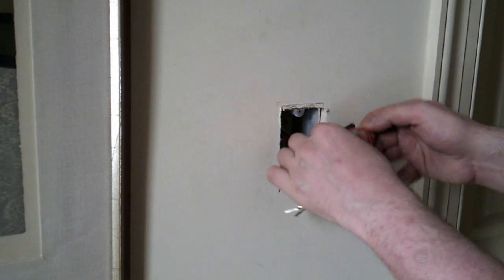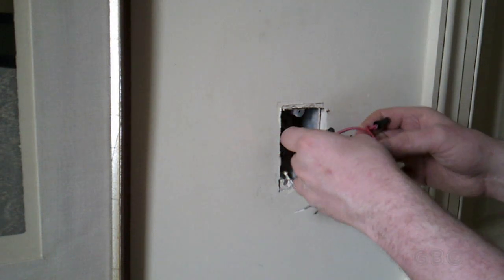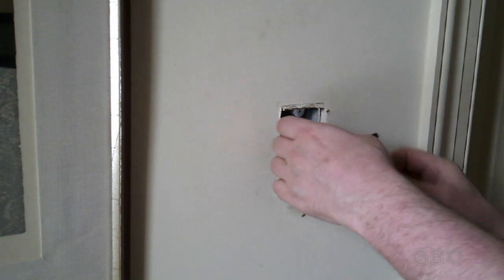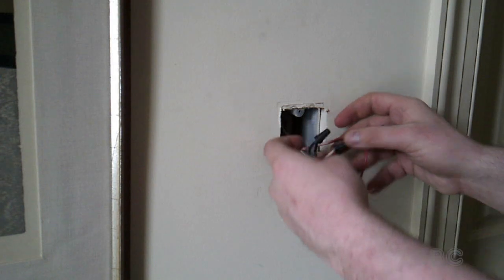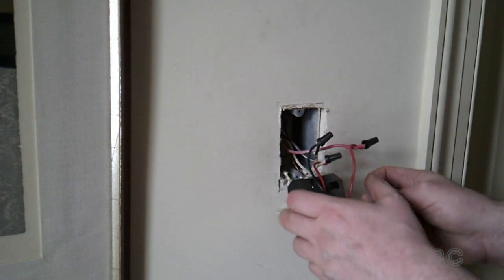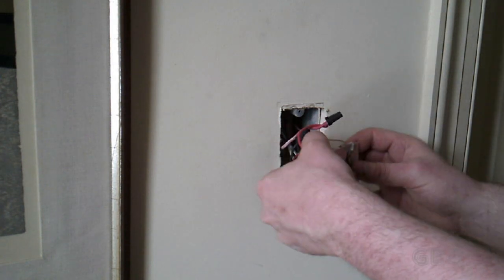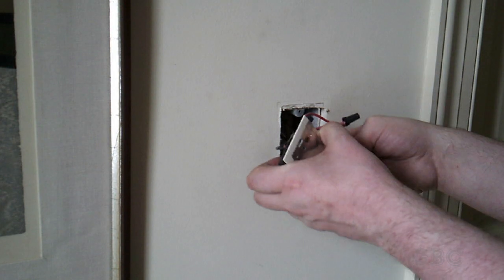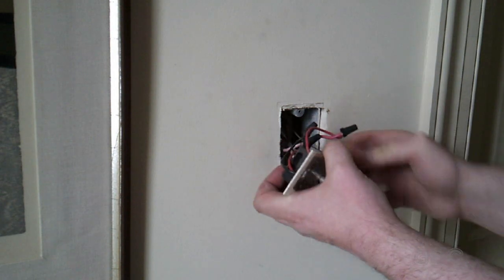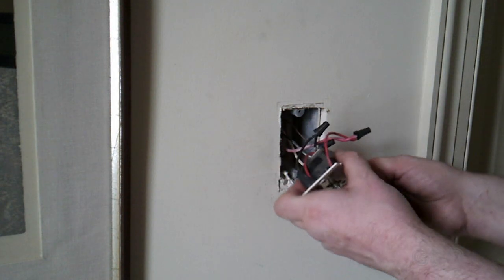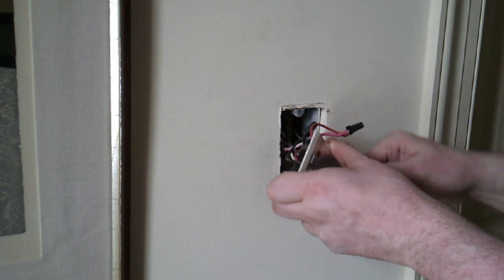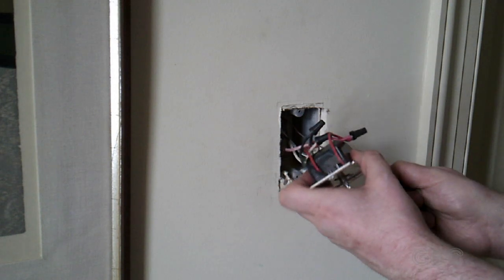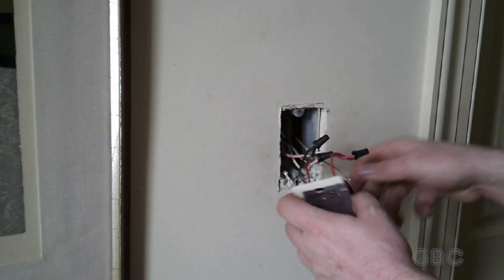The two red wires in this case are the traveler wires that go over to the other switch. The black wire is either the power wire or the feed wire to the light. And of course there's a ground wire which I am disconnecting right here.